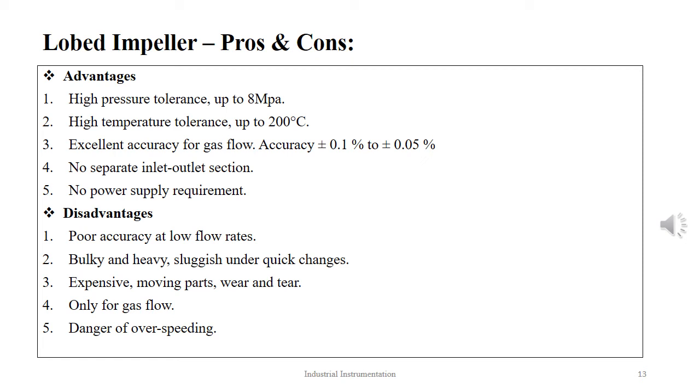However, the disadvantages are poor accuracy at low flow rates, bulky size, heavy and sluggish under changes, expensive, moving parts that suffer from wear and tear, only good for gas flow, and danger of over-speeding.